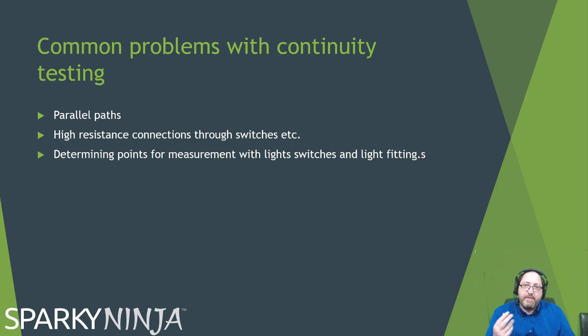Common problems with continuity, we've mentioned the parallels. Other things that could be a problem is when we go through light switches. So if I'm measuring at the switch line and I've gone through the switch to get to the switch line, if I'm buying my light switches from some bucket in a car boot sale or something, or probably the latest MK ones, I'm going to have some high contact resistance. So it might be that the switch is naff, but they can actually start spiking up your resistance value. Sometimes a good couple of switches might help. It might be that you've recognized a faulty accessory and you've got to bin it. I don't know. But sometimes if you have spiking measurements, it might be a connection or a switch that's created the problem. It might not be conductor length or size.